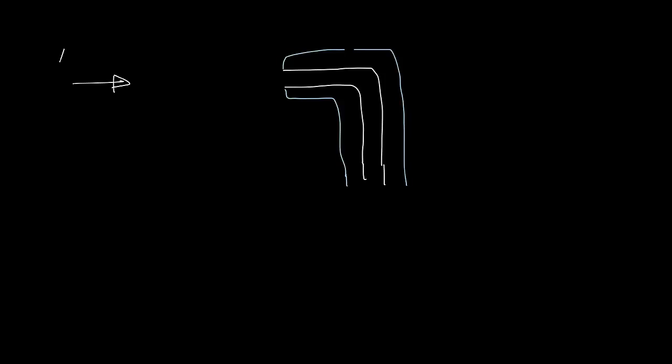So the inner tube has an opening that faces forward. The outer tube has one that's perpendicular to the front of the pitot tube, so probably on top right here. Now if you point the pitot tube into the direction of airflow, this front opening will be measuring total pressure. And on top, since there's no velocity in this direction, it's only seeing static pressure.